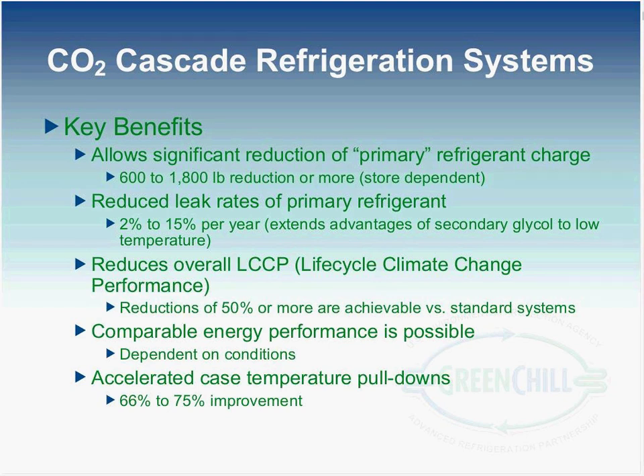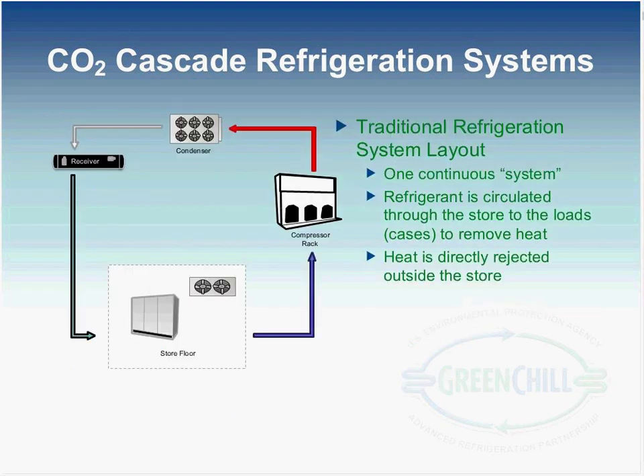Very good performance. And one very important thing to note here is that you're also going to have the opportunity for some accelerated case pull downs after defrost. We're looking at somewhere on the range of 2/3 to 3/4 reduction, so that's very, very good performance there. Move on to a little bit about explanations, and first I'm going to reground on the traditional system.